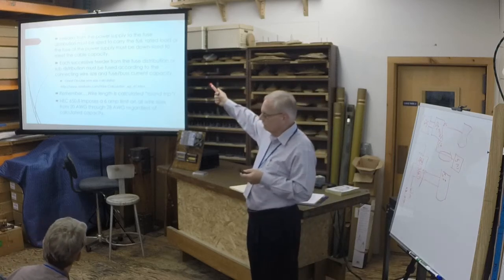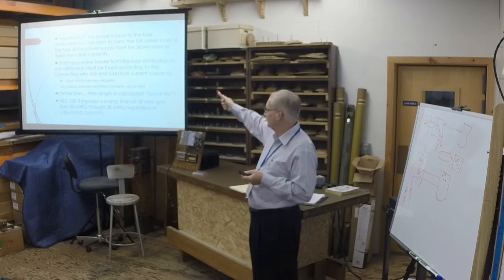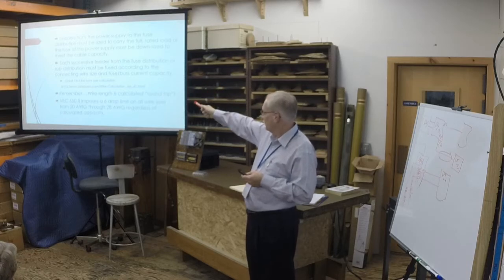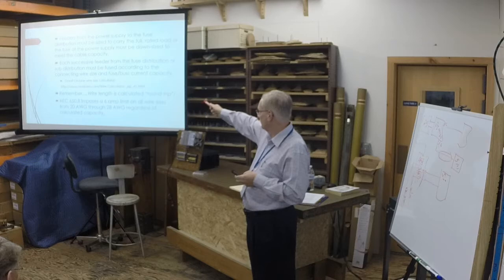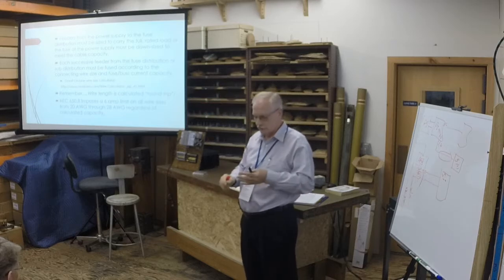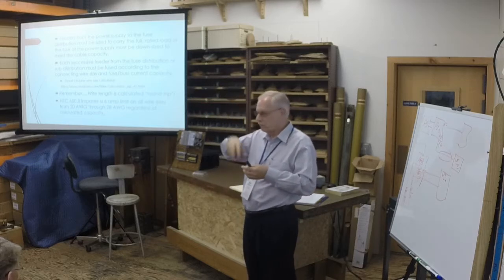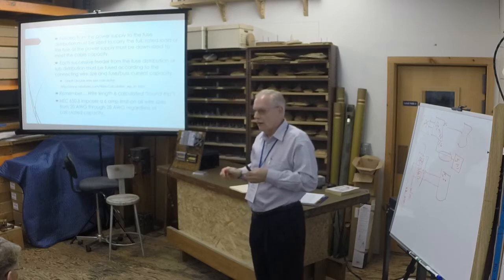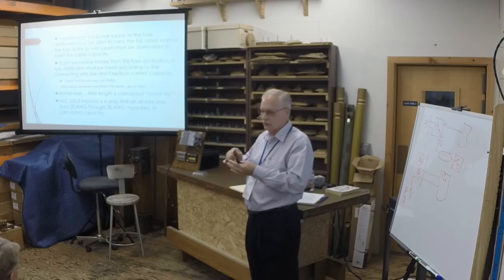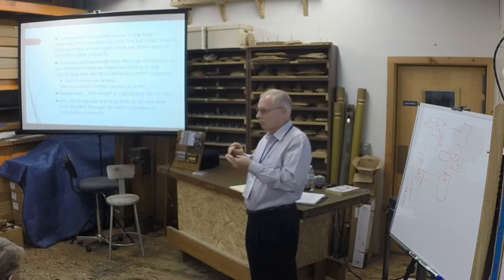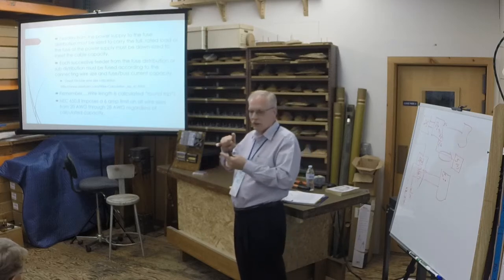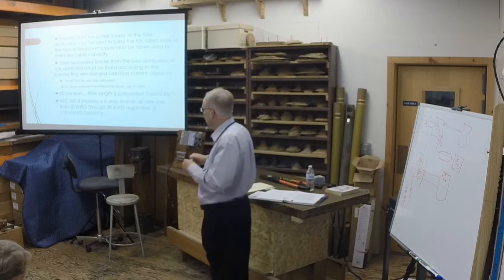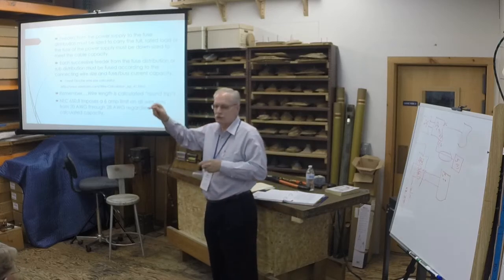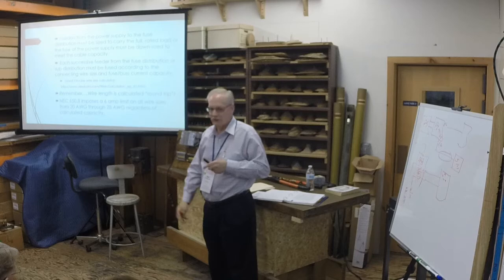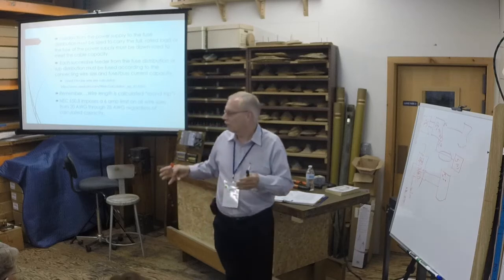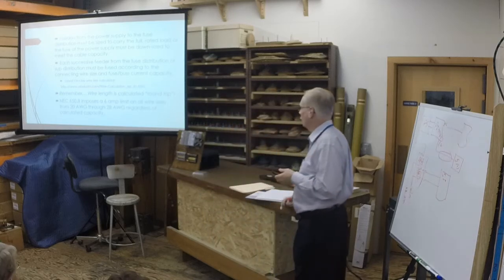That's just what I was talking about. Fusing to meet the size of the cable. Each successive fuse, there's a calculator. Wire Barn, it's a great little calculator. It asks you for 4 or 5 points of data, what you want. It'll ask you how far you want to go, what voltage drop you want, what voltage you're operating at, and it'll give you out to tenths or hundredths of a foot what the size cable is and how far you can go. So it's a great little piece.